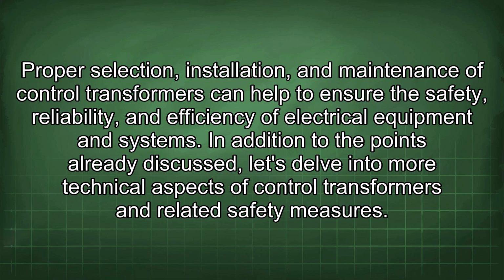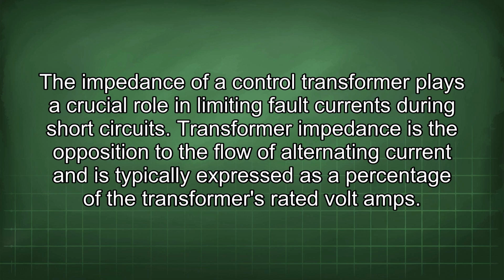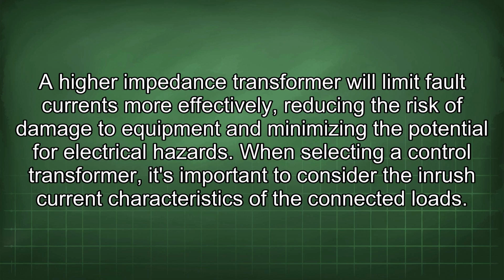related safety measures. The impedance of a control transformer plays a crucial role in limiting fault currents during short circuits. Transformer impedance is the opposition to the flow of alternating current and is typically expressed as a percentage of the transformer's rated voltamps. A higher impedance transformer will limit fault currents more effectively, reducing the risk of damage to equipment and minimizing the potential for electrical hazards.